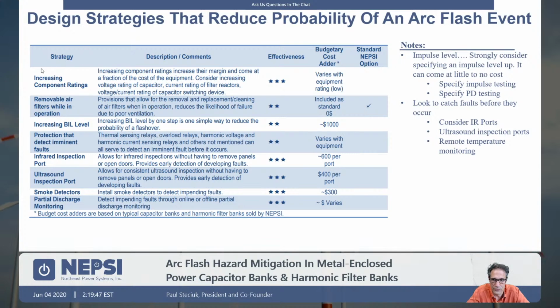Always think about increasing the component ratings. The cost to increase component ratings come at a fraction of the cost of the equipment. If you have a 13.8 kV system, it's rated 7.96 kV line to neutral. You don't need to pick a 7.96 kV rated capacitor. You can go to 8.32 kV, 9.54 kV. By increasing that capacitor voltage rating by 10 or 20 or 30%, you bring the failure rate from 1 in 5,000 to potentially 1 in 10,000 or 1 in 15,000. The cost difference is insignificant.